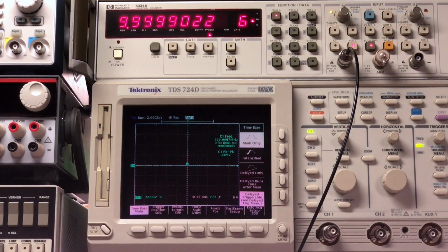So the frequency, it looks like it is under 10 megahertz, but not by too much, but that really should be right on at 10 megahertz. So that does match up with that idea that there is a calibration problem, that CalD error that came up. But it's, again, not too far off, so good to see, but it does need some adjustment. So the next thing that I will do is to open the top of the instrument, and let's take a look inside. And let's see exactly what's going on with this calibration problem and that CalD error. I'll reposition the camera and I'll be right back.